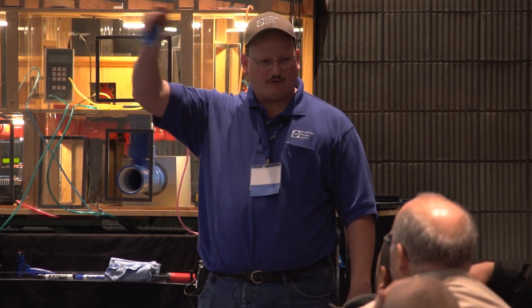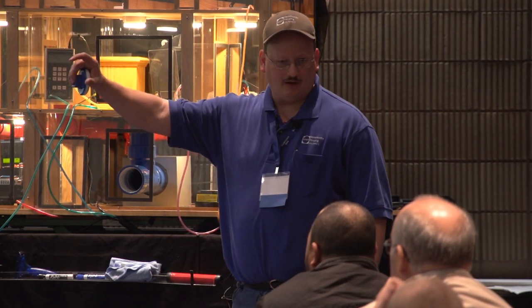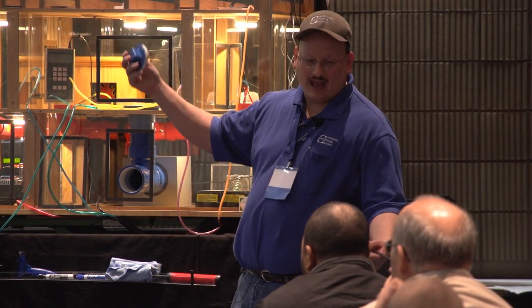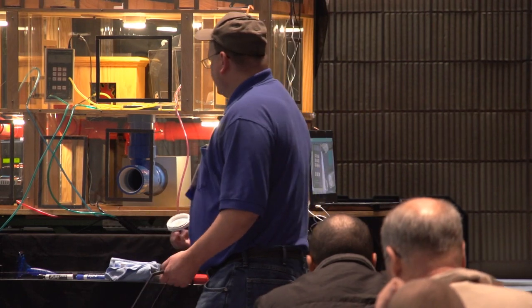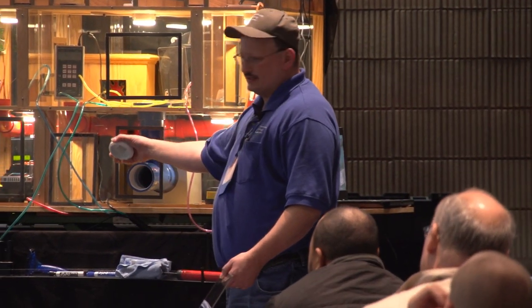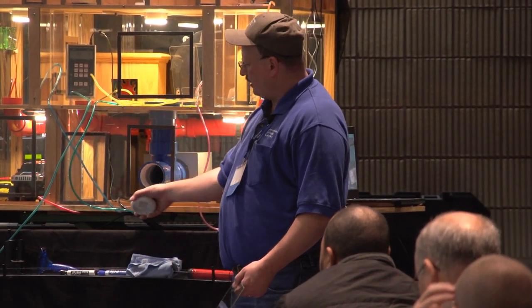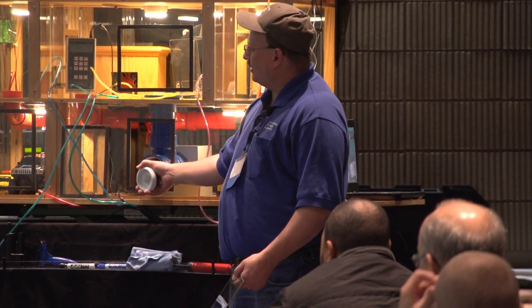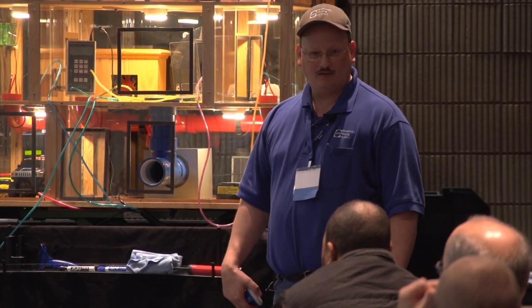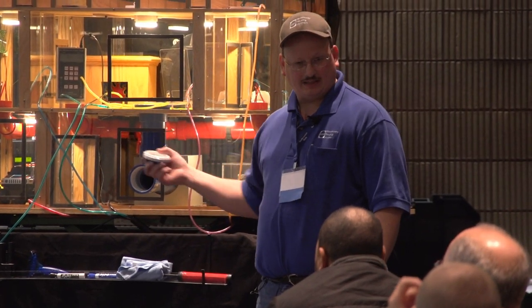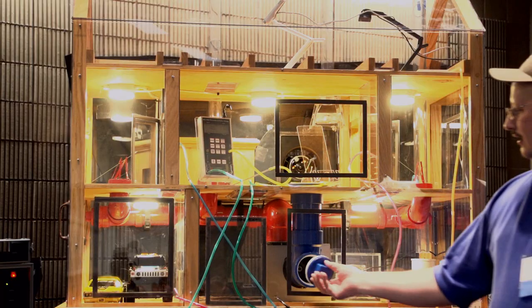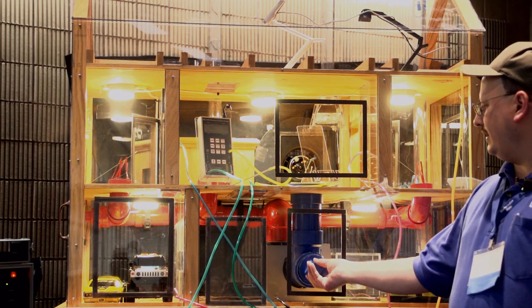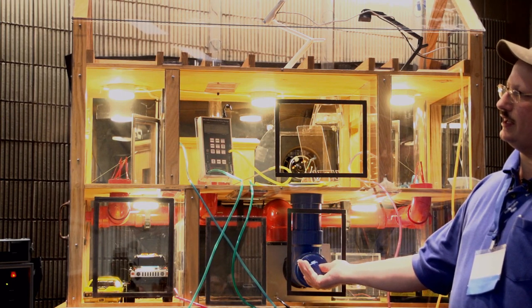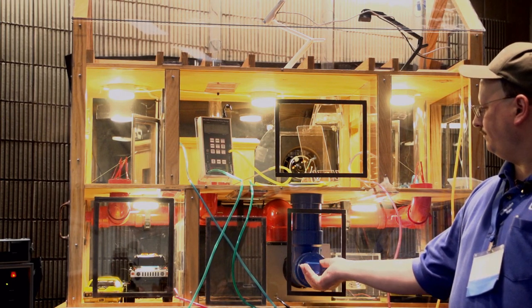It is. Is that moving indoor air through that duct? Yeah. So you'd want that sealed and insulated, right? If it's in an attic or an unconditioned space. So let's say this is an unconditioned crawl space, and that duct is open like that, would that affect my blower door? Because my ductwork is connected to the interior of the space, right? Yeah. So we can seal that up. And I have leaks on the supplies and on the returns.